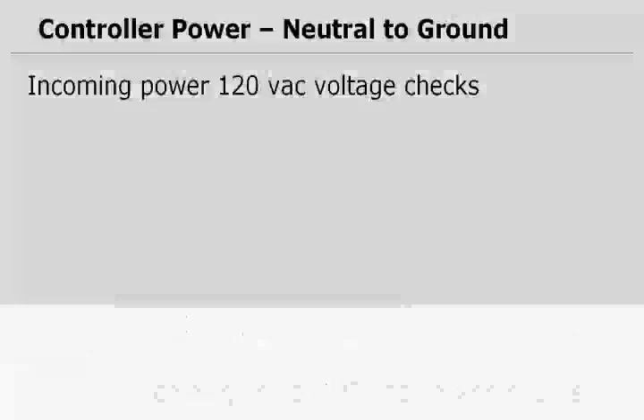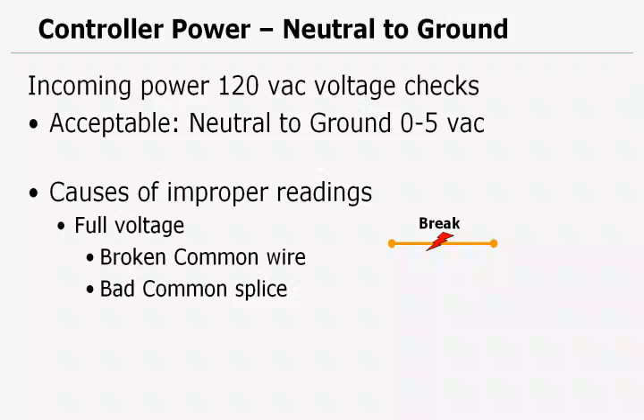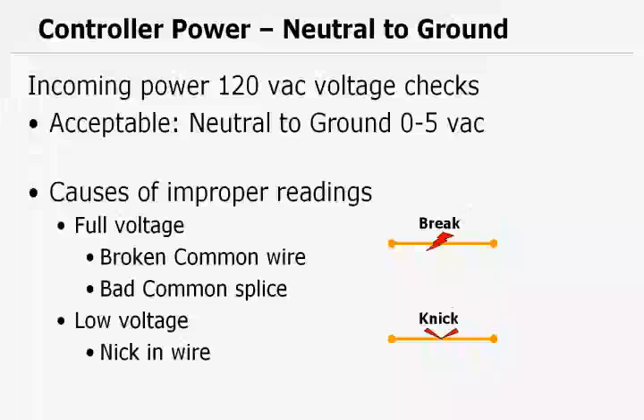Let's drill into that a little bit more. 0 to 5 volts is an acceptable reading. The causes of an improper reading: if we had a full voltage reading, something around 120 volts, we might have a broken common wire. The common wire, the neutral wire, could be broken. We could be somehow pulling voltage from the 120 volt hot wire. A break is going to do that if it's broken in the right way. And a bad common, causes of improper readings, or for a full voltage reading, we might have a broken common wire where it's inducing voltage into the hot wire, or we might have a bad common wire splice. If we have a low voltage reading, it could be a nick in the wire, or it could be a bad splice. So those are the things that we're looking for if, when we read the neutral to ground, we have something more than 5 volts.